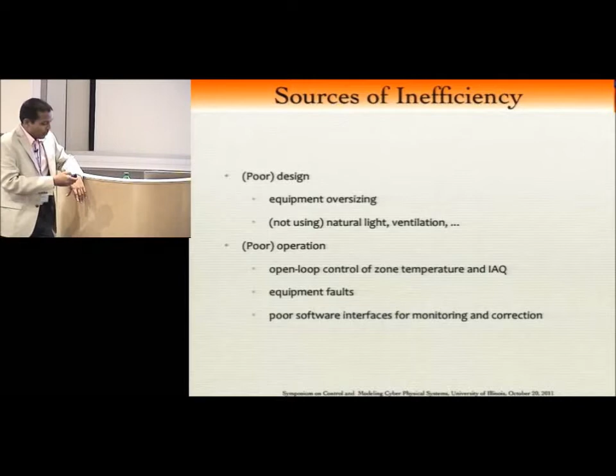But it's still open loop in the sense that the building, after all, exists for its occupants, right? But in all of this control, the occupants really play no role. So it doesn't even pay attention to how many occupants are there. And there, of course, are equipment faults that it doesn't pay much attention to, as long as there are no comfort complaints. And poor software interfaces, I guess I'll come to that towards the end. Right now, it won't make a whole lot of sense. So that is what I mean by open loop control, and what happens because of it.